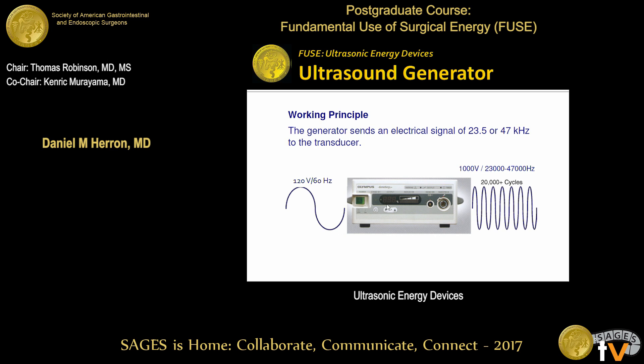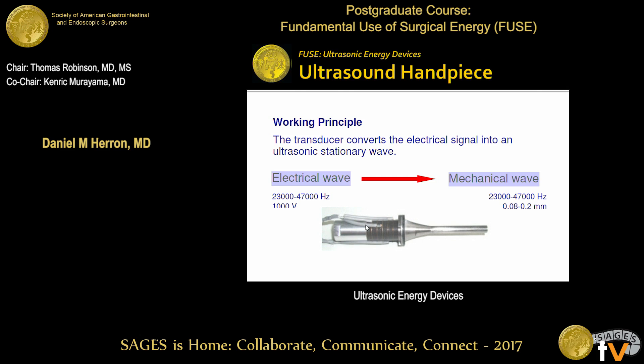You may have a controller box which looks something like this. The wall current is coming in from the electric plug at 120 volts, 60 hertz or 60 cycles per second. What this box is doing is converting it to a much higher voltage and a much higher frequency — depending on the brand, somewhere between 20 to about 50,000 cycles per second. This electricity is what gets passed to the handpiece, and this is where the electrical wave gets converted into the mechanical wave.